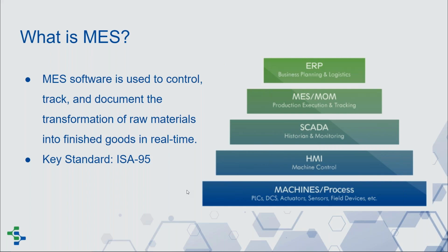So you're probably familiar with the control layer or the machine layer, right? Here we're talking about PLCs, and this is a category that is physically involved in the process of manufacturing materials. So directly controlling the starting and stopping, the opening and closing, all of those types of things, right? And typically we have to do that very rapidly, right? So we're talking about single digit, maybe double digit millisecond time scale. The data is pretty simple, on or off. Of course, there's examples where logic and data gets more complex at the control level, but as a general rule of thumb, we're talking about Booleans and just primitive data types and things like that, right?